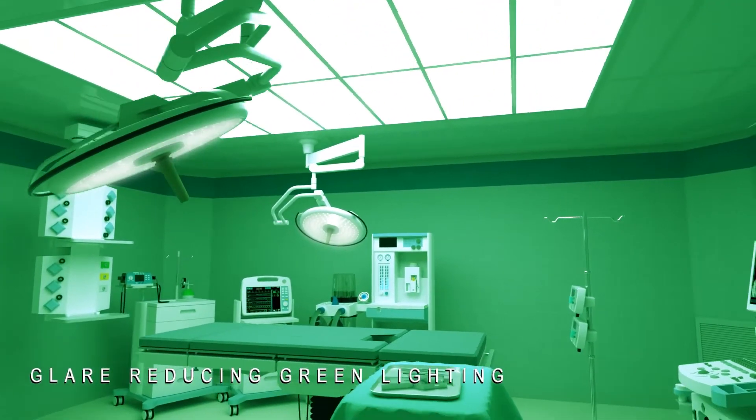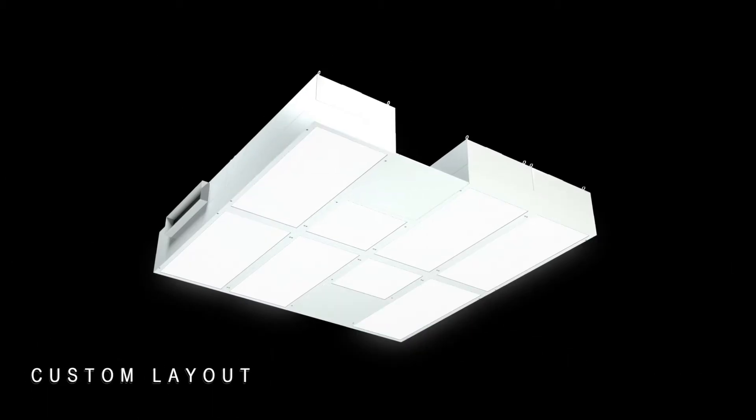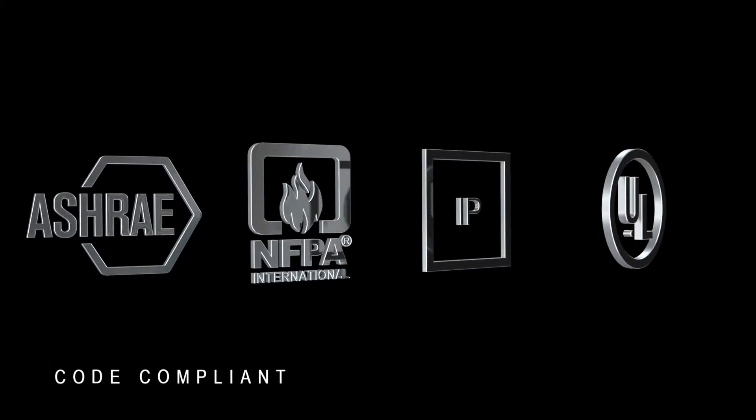You don't want any shadows, and you don't want to either over-cool or overheat the person being operated on. Using the ceiling grid system, the engineer can confirm that we are meeting the ASHRAE requirements for how much airflow and light is going to the specific spaces. That was a great add-on product. We also coordinated with the boom manufacturer and made sure we had access panels for medical gas and other utilities above the ceiling.